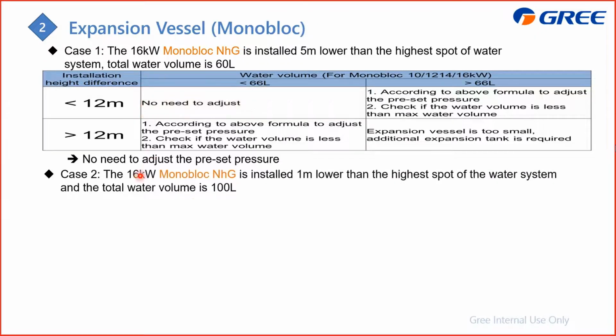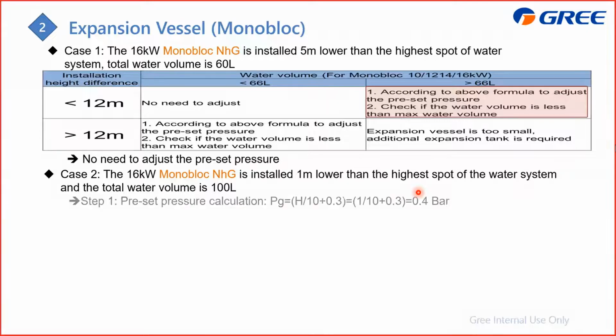Case 2 is also the same, a 16 kilowatt monoblock, but this time it is only 1 meter lower than the highest spot, and the total water volume is 100 liters. So for this one, it goes to this part because 100 is higher than 66 liters, which means you need to adjust the inside pressure. According to this formula, you can get the new PG, which is 0.4 bar. Also, you can find that this H is this 1 meter.